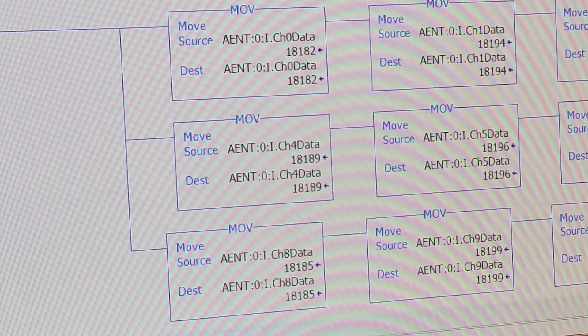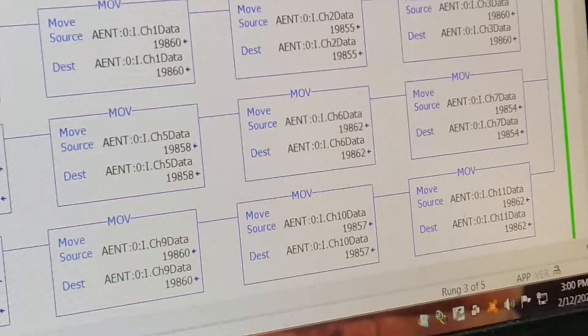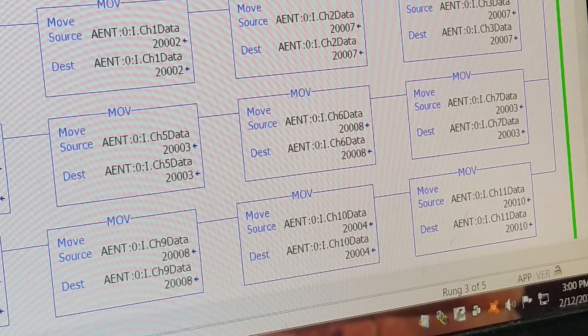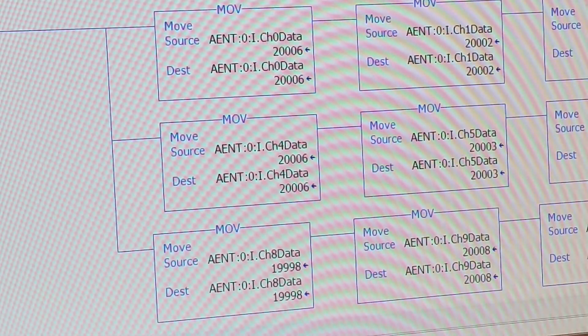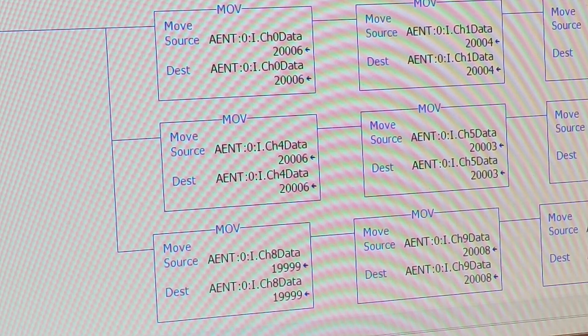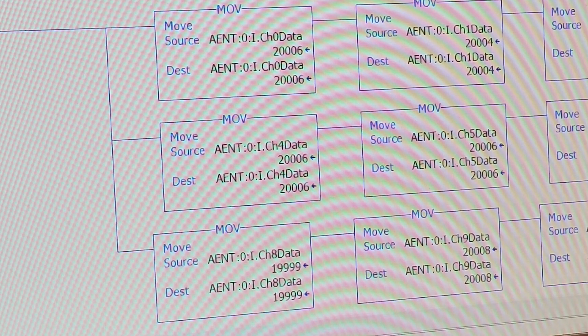So we've proved that our current channels on all 12 channels, over here, they're all working. So that means at the same time, because each channel is wired back individually, all of our output channels are working. So if you're testing these things, best to do it on a bench. Take your time, take you an hour or so to get everything set up if you're doing it from scratch. And you'll have a lot more success in having good quality settings.